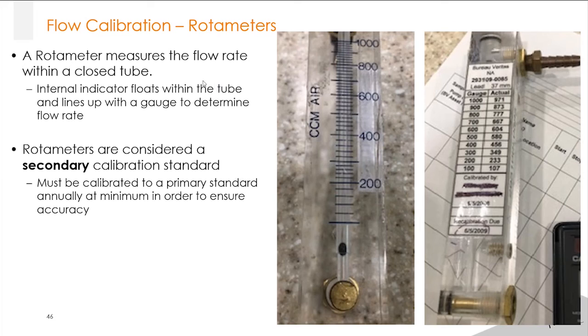All right, so rotameters. If you're doing any air sampling, you may have come across this already. The rotameter is just measuring the flow rate. It's considered a secondary calibration standard, so more qualitative, you could say. The rotameter needs to be calibrated to a primary standard at least annually to ensure accuracy. A primary standard is something you actually send to a lab, and you get a NIST traceable calibration certificate for it. This is what you need to prove that it is reading correctly.